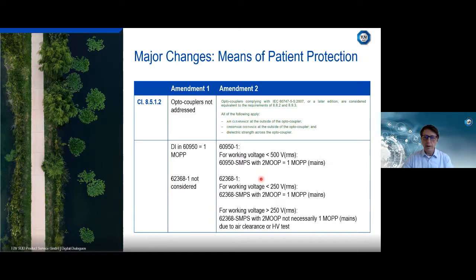For a power supply with 62368, this is a little bit different, and the voltage is lower. Only when the working voltage is below 250 volt does this apply, that the two means of operator protection are identical and can be used as one means of patient protection. When it's above this voltage, it's not necessarily identical, and you have to pay attention to air clearance or high voltage test. So be careful when you use a power supply having a certificate of 62368, and have a close look whether you can use it as a means of patient protection or not.